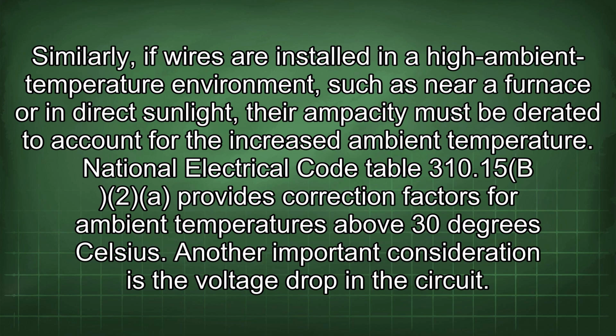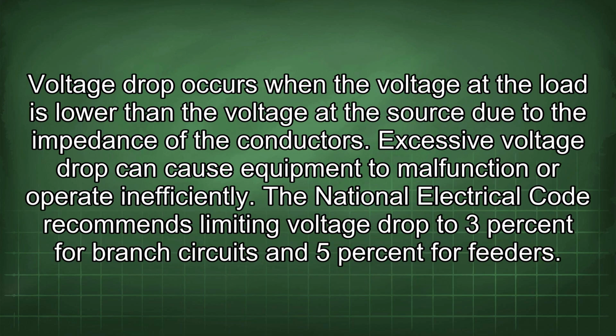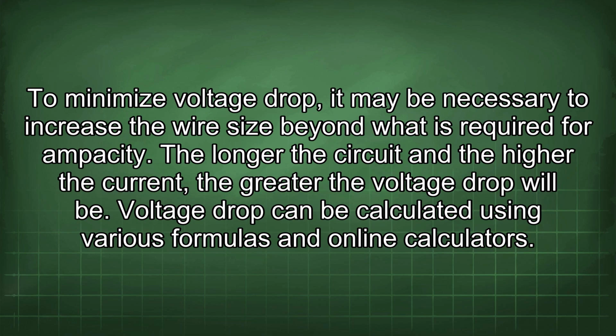Another important consideration is the voltage drop in the circuit. Voltage drop occurs when the voltage at the load is lower than the voltage at the source due to the impedance of the conductors. Excessive voltage drop can cause equipment to malfunction or operate inefficiently. The National Electrical Code recommends limiting voltage drop to 3% for branch circuits and 5% for feeders. To minimize voltage drop, it may be necessary to increase the wire size beyond what is required for ampacity. The longer the circuit and the higher the current, the greater the voltage drop will be. Voltage drop can be calculated using various formulas and online calculators.